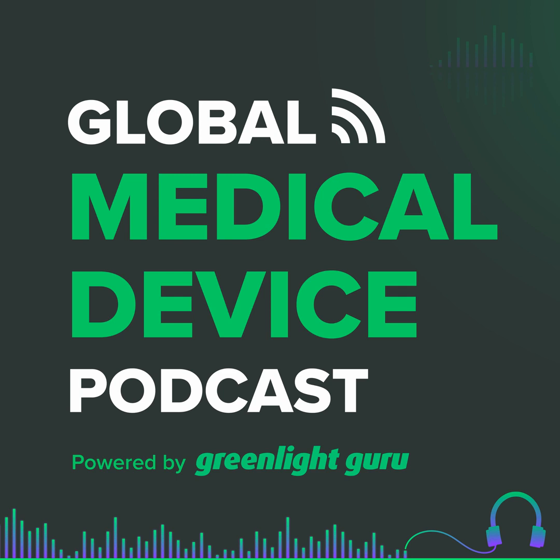Then, a couple of years later, in 2022, Congress expanded FDA's authority, and it now applies. This is the FDORA that you mentioned earlier. It now applies to any medical device on the market. So, not just limited to SaMDs, not just limited to AI or ML or anything like that. Any medical device on the market may use a PCCP to make changes without, and this is the important part, Etienne, without requiring a new pre-market submission.